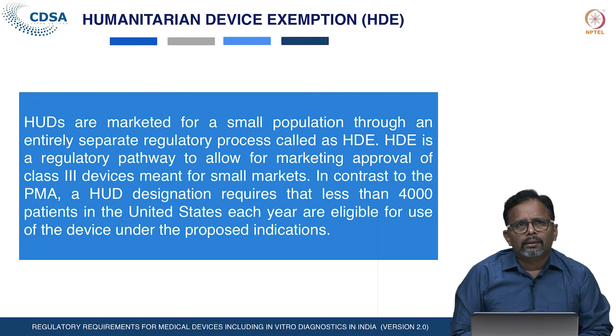After granting the HUD designation of the device, the HDE is for the approval of the intended use. Unlike the PMA approval, under HDE the sponsor is not expected to submit clinical data to the FDA to prove the safety and efficacy, but they must submit sufficient data proving that the device does not pose any unacceptable risk and that the probable benefit of the device outweighs the risk. For HDE devices, there is no specific requirement for clinical data, though the manufacturer has to submit data assuring that there is no unacceptable risk posed by the device and that sufficient data is available to prove the benefit of the particular device in a certain population.